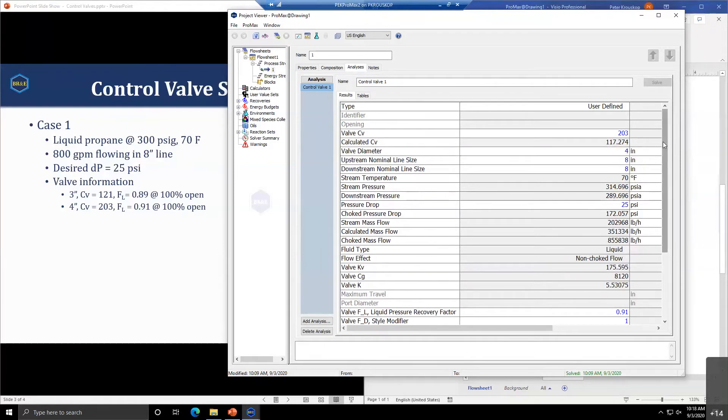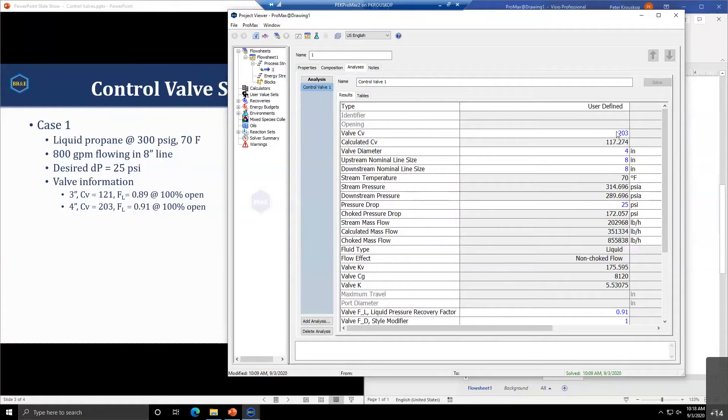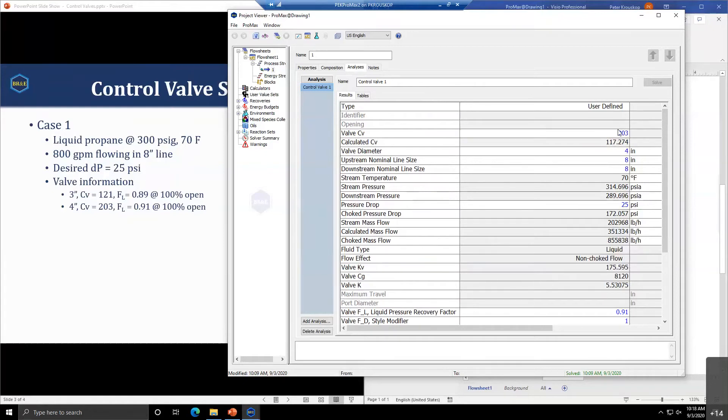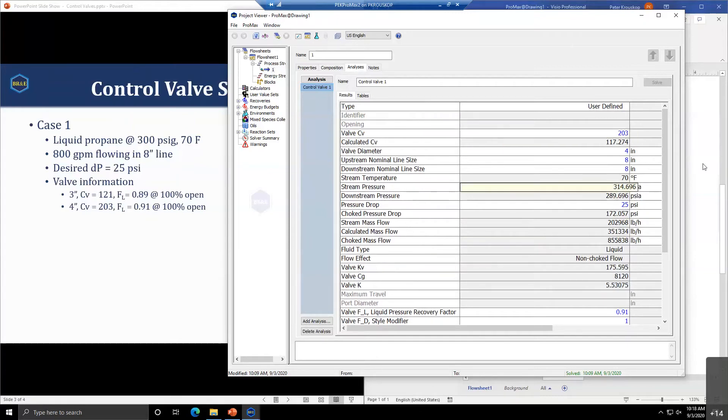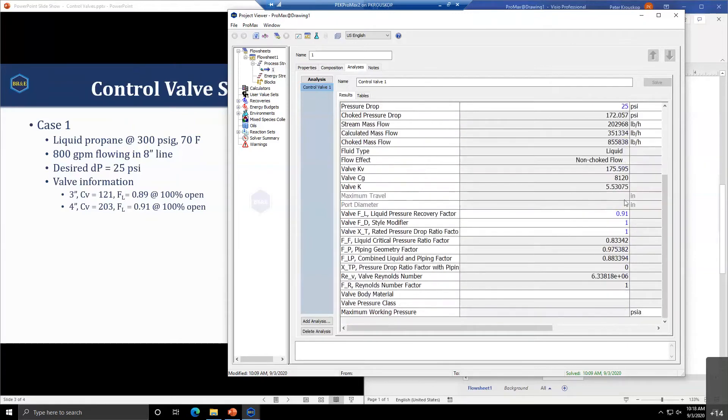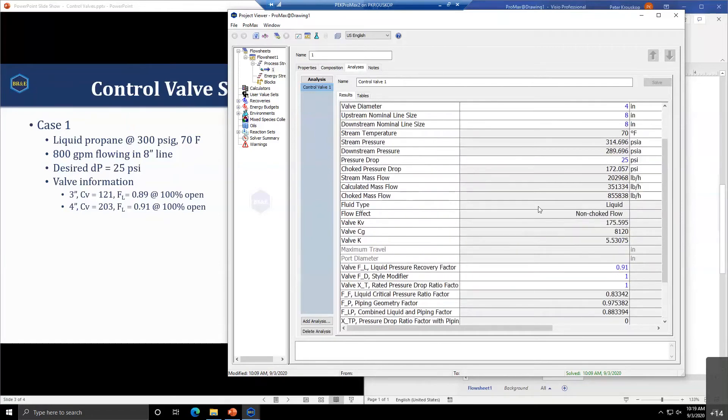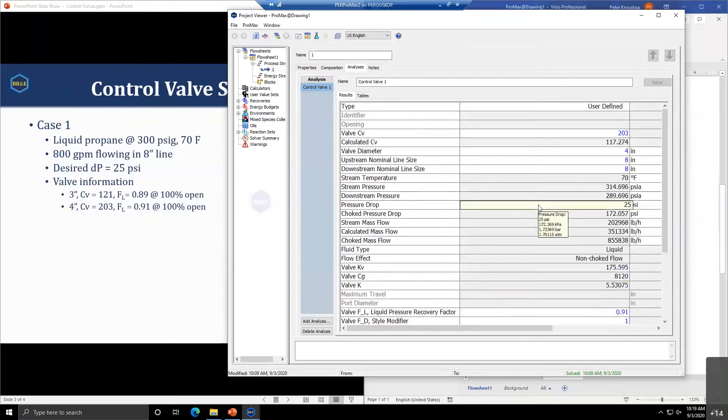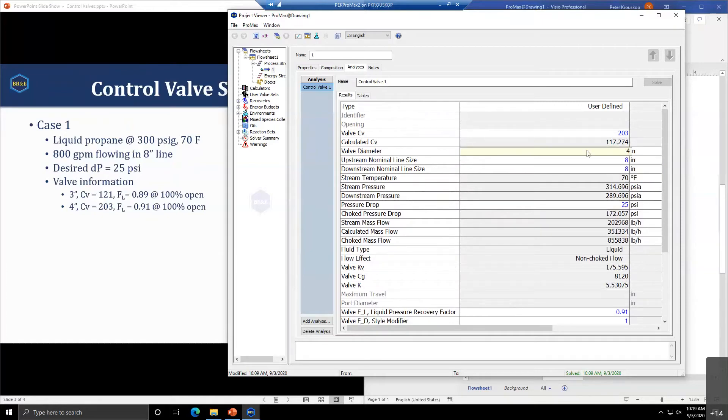These are effectively globe valves that we have, but in reality they could be pretty much any type of control valve. As long as you know the appropriate parameters for the equations in the Fisher handbook, you can use this analysis to obtain a size. We have determined our three-inch valve was too small and our four-inch valve will work.